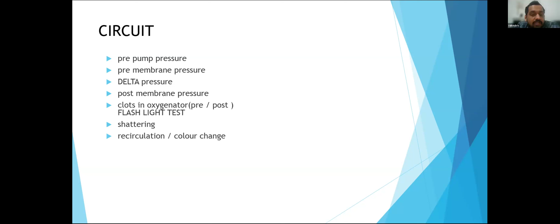And then the recirculation part and color change on the circuits, the venous and arterial, should be monitored. ABG of the circuit should definitely be monitored. Pre and post membrane ABG should be monitored. Remember, guys, when you are taking pre and post oxygenator ABGs, FiO2 should always be 1 here. And any circuit which is normally working in case of an ECMO should oxygenate at least 4 times of your pre-membrane. Length of the cannulas, as I quoted earlier, should be monitored based upon where they were fixed. Pump head auscultation technique.